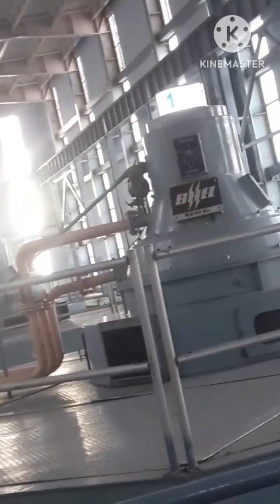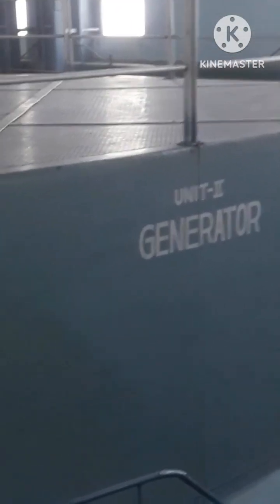After entering the hydropower plant, if we want to see the rotating of the turbine, the turbine shaft and the other parts, we have to get into the downstage. After getting there, we can see the turbine rotation and the other parts inside the plant. Here we can see the wicket gates. What is the main purpose of these wicket gates? These wicket gates are adjustable vanes which are in series. The main purpose of these wicket gates is to control the flow of water at the turbine.